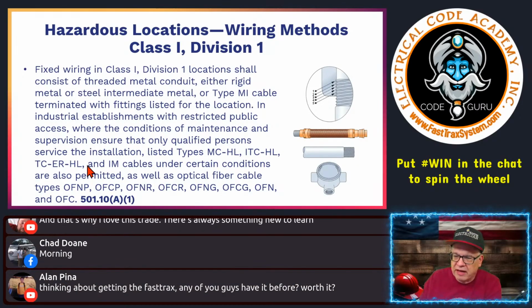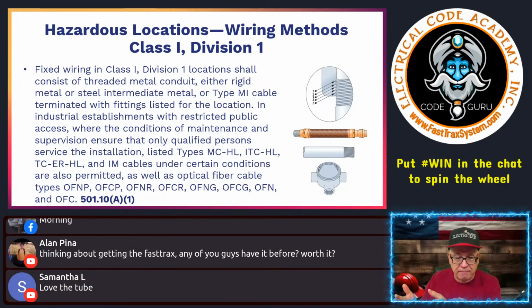And then, of course, you have IM cable, under certain conditions also permitted, as well as optical fiber cables, type OFNP. So if you have an optical fiber application, these are the wiring methods allowed in a Class 1 Division 1. And you'll noticeably see some things that are missing.